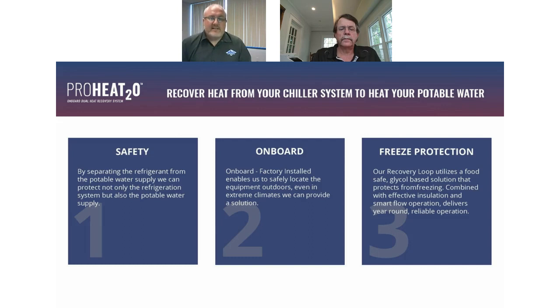One is safety. By separating that refrigerant from the potable water supply, we can protect not only the refrigeration system, but also your potable water supply from any contamination. It's on board, so everything's factory installed, and that enables us to safely locate the equipment outdoors. Even in extreme climates, we can provide a solution. For freeze protection, our recovery loop utilizes a food-safe glycol-based solution that protects it from freezing. Combined with the effective insulation and smart flow operation, we deliver year-round, reliable operation of the system.